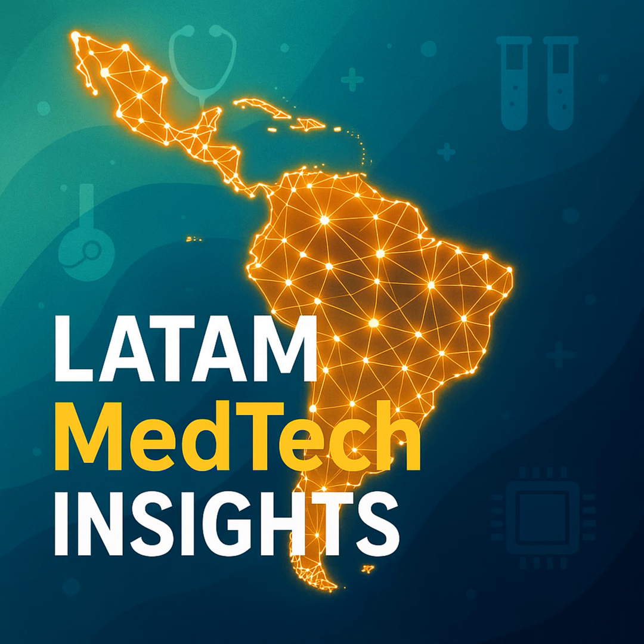For example, a company producing orthopedic implants in Monterrey had their GMP certification delayed for months. The reason was their supplier for titanium alloy, based in another country, did not have documentation that met the specific traceability requirements outlined in NOM-241. The Mexican manufacturer had to conduct a full on-site audit of their supplier and completely overhaul their receiving and inspection process to gain compliance. This case highlights that simply having an ISO 13485 certification is not enough. Your QMS must be specifically adapted to the nuances of NOM-241.